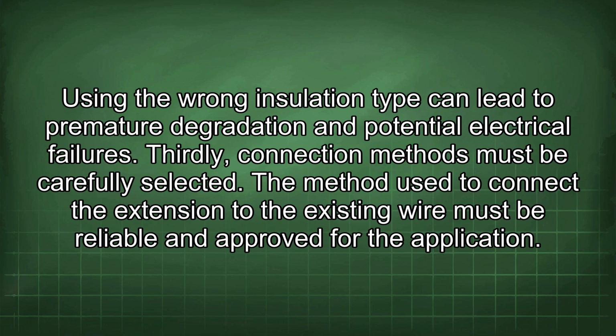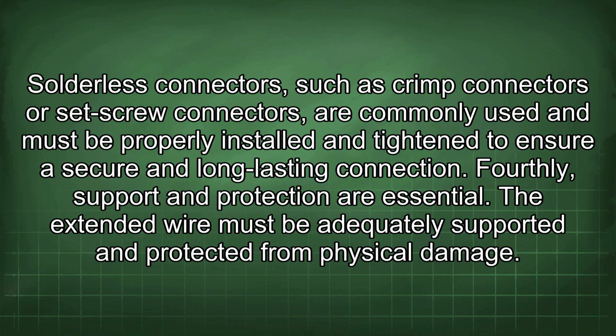Thirdly, connection methods must be carefully selected. The method used to connect the extension to the existing wire must be reliable and approved for the application. Solderless connectors, such as crimp connectors or set screw connectors, are commonly used and must be properly installed and tightened to ensure a secure and long-lasting connection.